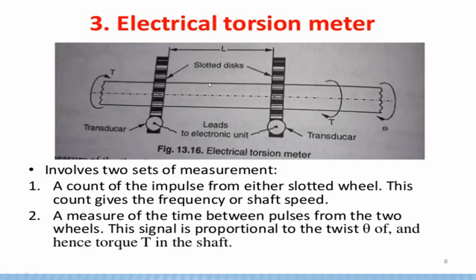You can see the slotted discs. These are the two slotted discs. These are used to count the frequency or shaft speed. These slotted discs are used to calculate the speed. And the second one, a measure of the time between the pulses from the two wheels. This signal is proportional to the twist theta of the shaft and hence torque T in the shaft. It measures the time between pulses from the two wheels.